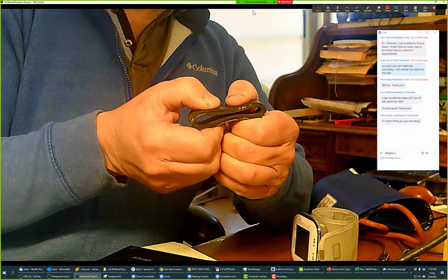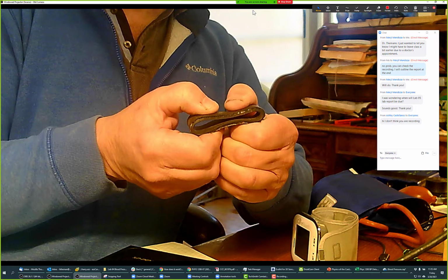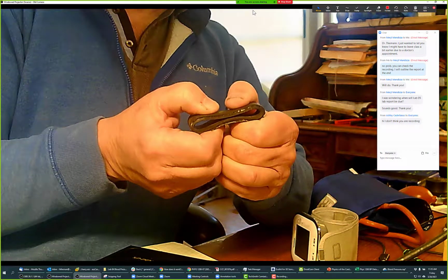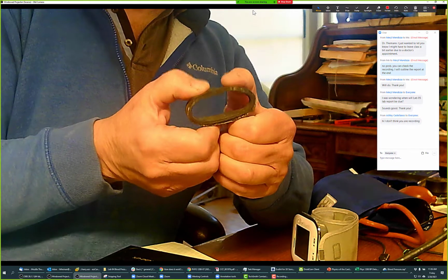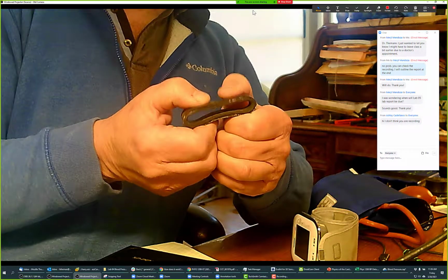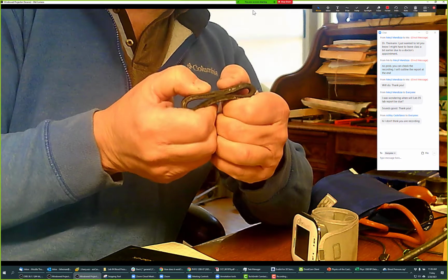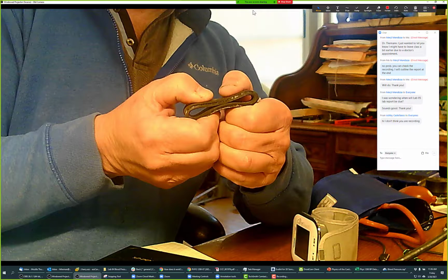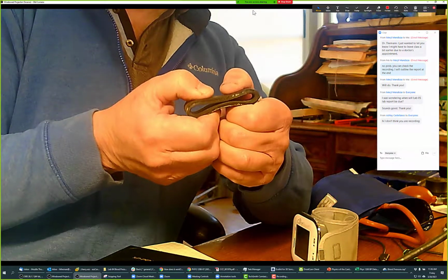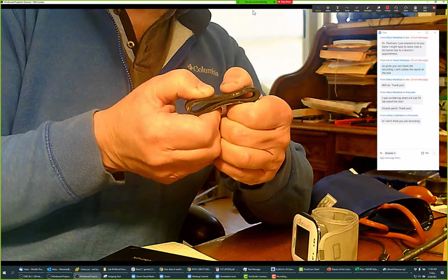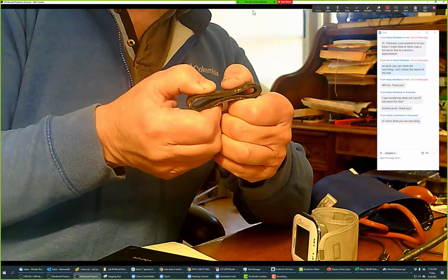But in our case, the pressure cuff is still telling us a pressure, and our arm is still flexing, but the lowest pressure is no longer here. So we have to find a place where the swing that goes down below the average pressure is the maximum, because that's the point.